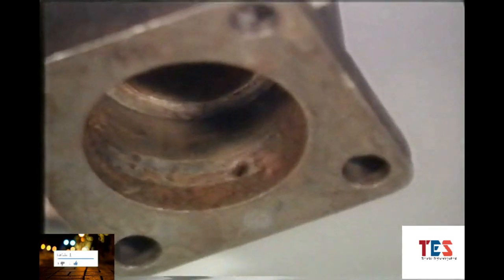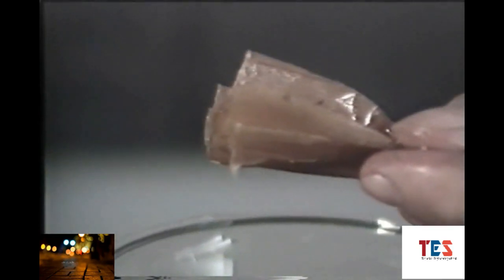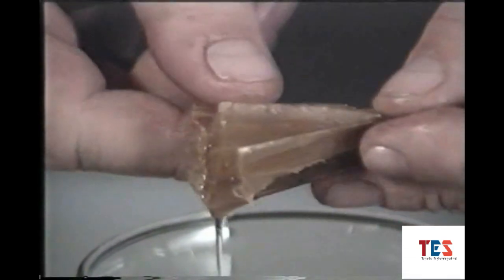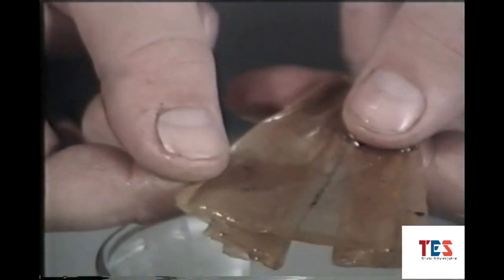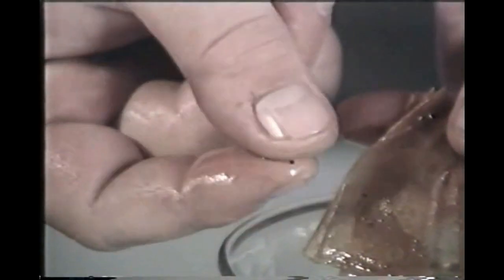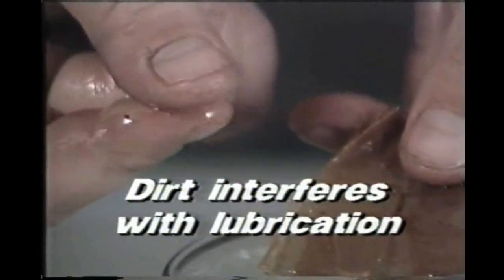Rust is not the only source of contamination in a fluid. Dirt is often responsible for much of the damage to components in a hydraulic system. Dirt interferes with the transmission of hydraulic energy by plugging orifices, and it reduces the ability of hydraulic fluid to release heat. The most significant problem, however, is that dirt interferes with lubrication.